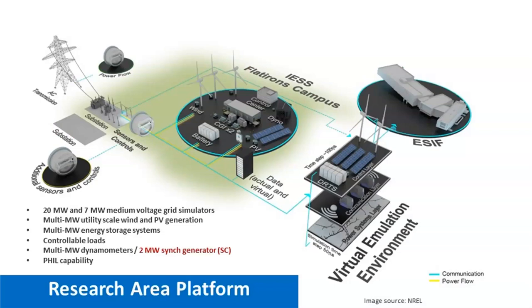platform at NREL's Flatirons campus. This is a high-level diagram of that, where we are trying to address all these issues by conducting testing, validation, and demonstration of different types of technologies at scale. We're currently pushing this system up to the 27 megawatt level, which is very large for a demonstration system of this type. We're in the process of adding a 2 megawatt synchronous generator to the system, and one of the use cases for that, of course, will be operating it as a synchronous condenser.